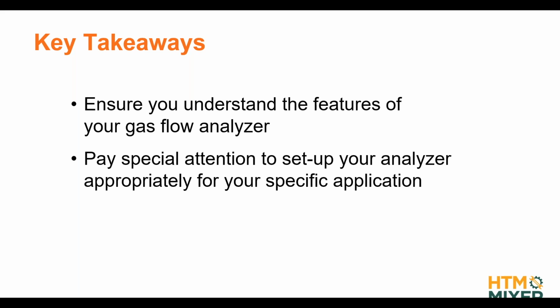And then pay special attention to the setup, like the settings of your analyzer, that it matches what you actually want to measure, and your device under test. If there's one thing, again, I want you to remember from this session, it is the gas standard. This has by far the highest impact. Make sure that you know the gas standard used by your device under test, and then set the exact same gas standard on your analyzer.